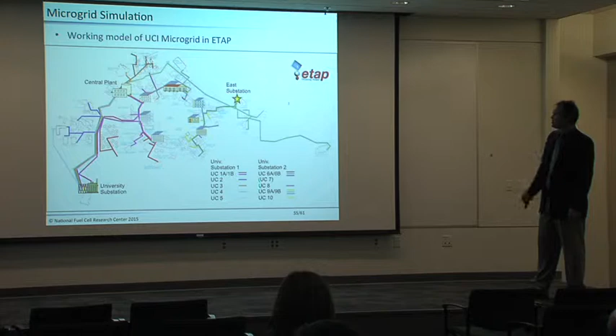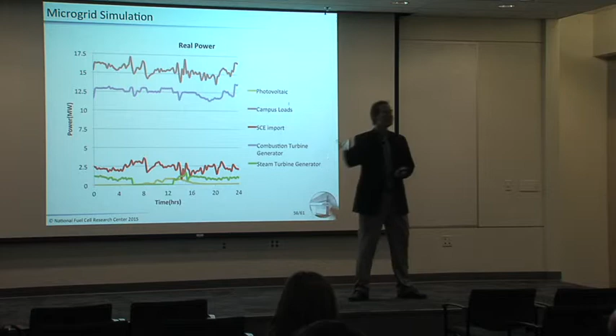We've simulated this using software from ETAP - you can see the various buses, the 10-12 kV circuits all right here, and this is the simulation of that campus. Notice our demand looks very flat - it still has dynamics, but it's essentially about 16 megawatts for the entire day, because we can dynamically dispatch the chiller plant and the gas turbine.